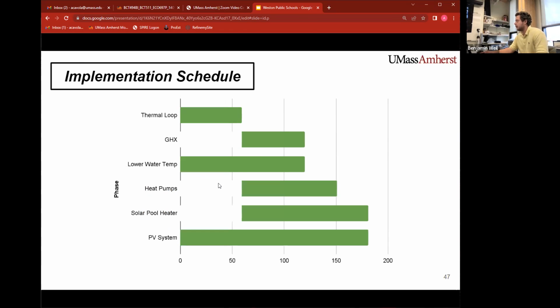So this is the implementation schedule of the different systems we proposed. The first thing you want to do is lower that water temperature. Lowering that water temperature allows the heat pumps to work better, the ground source heat exchanger to operate at that lower operating temperature, and the thermal loop to operate as it needs to. Once the thermal loop is installed, which you'd want to do first, along with lowering the water temperature as seen in this chart, you can then install the heat pumps, and then the solar pool heater, which will supplement the ground source heat exchanger and go into the thermal loop.